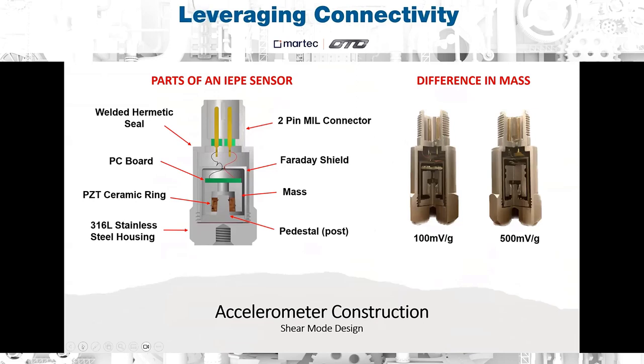Next, we can get into the actual construction of an accelerometer. So here are all the components that make up an IEPE accelerometer. The diagram on the left shows the internal design of the sensor, as well as all of the components. One thing that I'd like to point out is that this is a shear mode design. You can see this by the PZT ceramic ring attached to the mass. As this sensor vibrates up and down, the mass applies a shear force on the ceramic ring. The ceramic ring can then convert the mechanical motion into a measurable electrical signal. Shear mode design is extremely important as the output will not be affected by any type of higher temperature. Alternatively, some manufacturers utilize a compression mode design that will have defective outputs due to thermal transients.